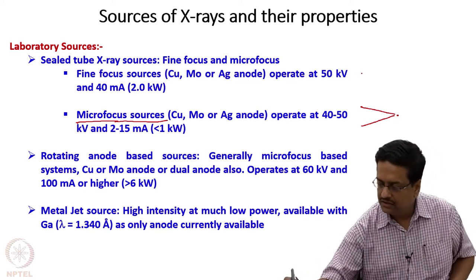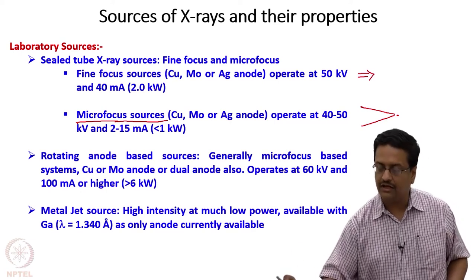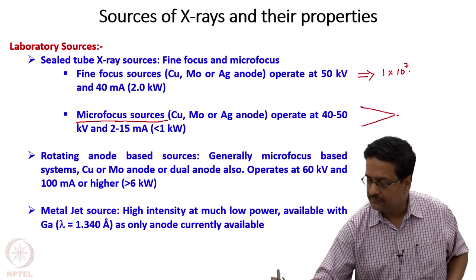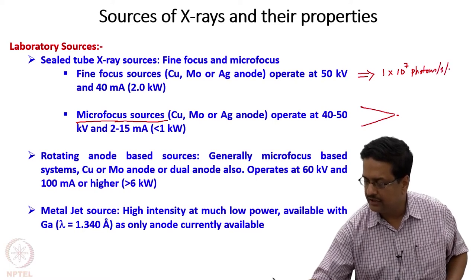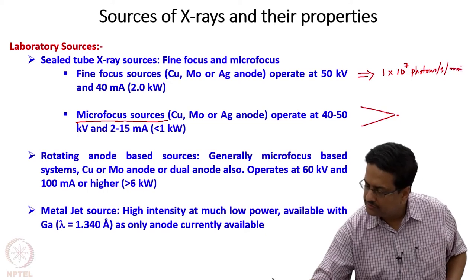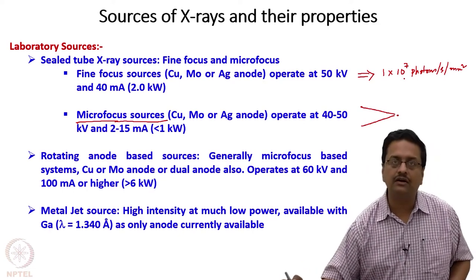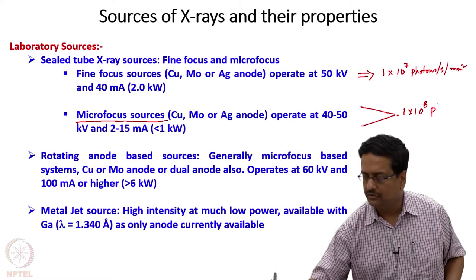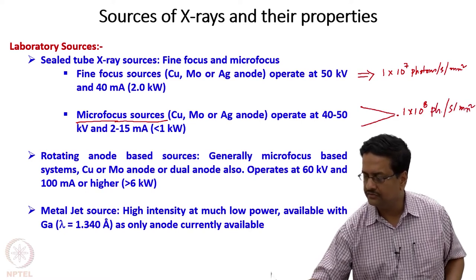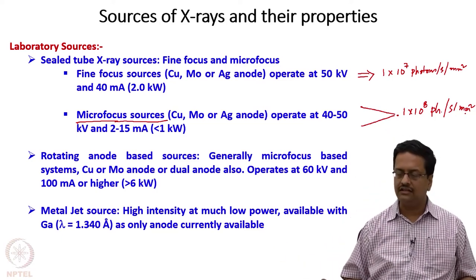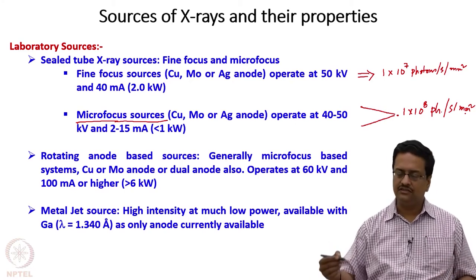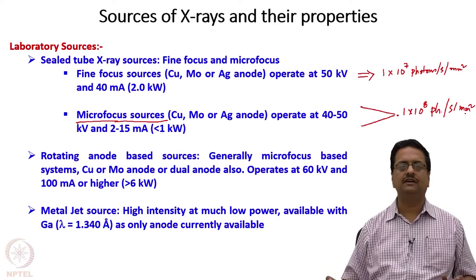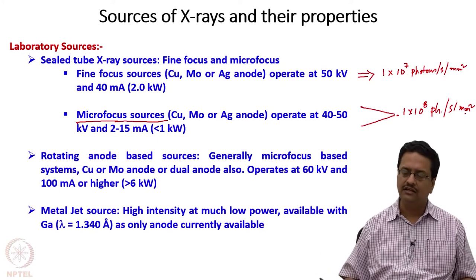As a result of this focusing, the intensity of the beam on the crystal increases. If we assume the intensity from a standard source on the crystal is about 1×10⁷ photons per second per square millimeter, micro focus sources give about 10 times increase in intensity on the crystal. As a result, data collection time will be reduced significantly — with micro focus sources we can collect data much faster instead of spending several hours using a standard X-ray tube.